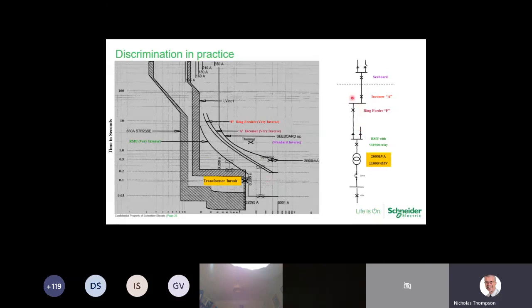The DNO will not move because they've graded on their network right up to 132 kV. Then we've got our incoming circuit breaker, which is our first circuit breaker, so that is that curve there. We can see we've now got a difference in curves: standard inverse on the DNO, and our incomer A on very inverse. We've mirrored that on the ring switch circuit breaker using a very inverse curve, and there is safety margin between the two. So we don't have our first circuit breaker curve crossing over the DNO curve, and we don't have our second circuit breaker curve crossing over the first one or over the DNO circuit breaker.